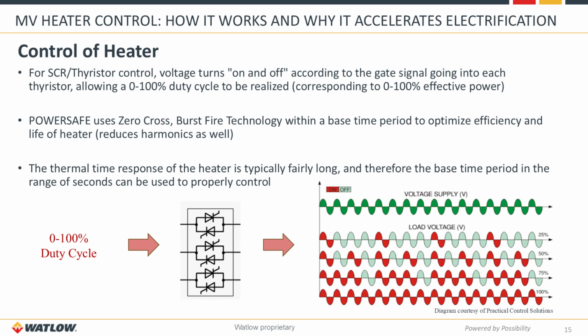heater itself. The thermal response time of the systems is typically fairly long. So you're heating a particular application here. You apply power to that. That power needs to be converted into heat. That heat then heats up the application media, whatever that may be. And therefore, that response time typically occurs over a couple of seconds. You could get faster, you could get slower, depending on your flow rates or whether you're in a boiler application. These base time periods can be changed within the systems, so you can react faster, or if you don't need to react faster, then you can set those higher and react slower.